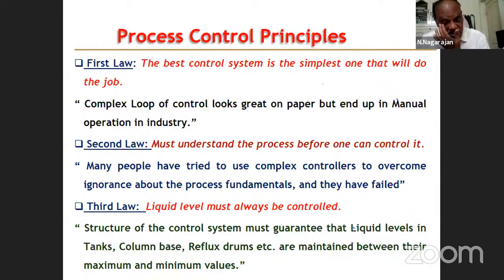Okay? The structure of the control system must guarantee that liquid levels in tanks, column base, reflux drums are maintained between their maximum and minimum values. They are allowed to float between the maximum and minimum values.